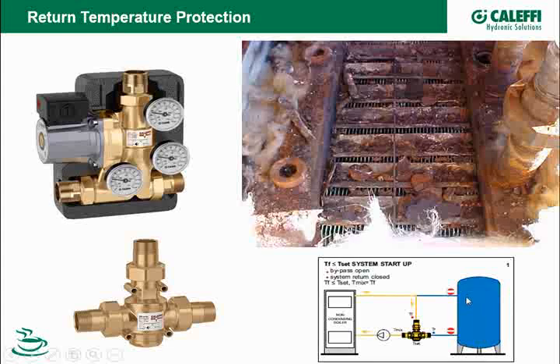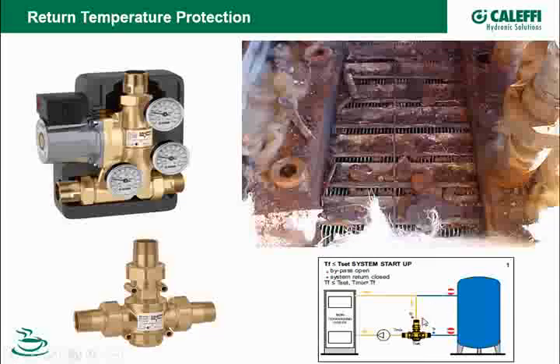Another thing that I'm seeing more and more of is guys adding buffer tanks to systems, especially systems that have a lot of small zones on them, and they're doing that even with condensing boilers to keep them from short cycling, to make sure they've got at least a 10, 15-minute run cycle every time they kick on. So they might go back and add a buffer tank. That's a good time to look at putting one of these little return protection mixing valves on it.